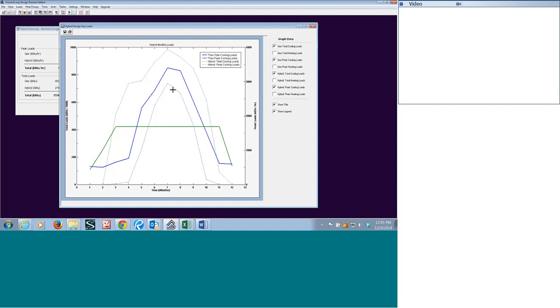So all of a sudden, you can see in a visual representation what your auxiliary cooling device should be capable of handling here. And it's making a pretty big difference on this cooling load. For whatever reason, the original load, who knows, maybe it was an intern in the original engineer's office, doesn't matter. This is what we've had to deal with, and on the forensics jobs that we see, I'd say probably less than 20% are an undersized ground loop. Most of them are usually related to bad controls, or rather a bad sequence of operation.